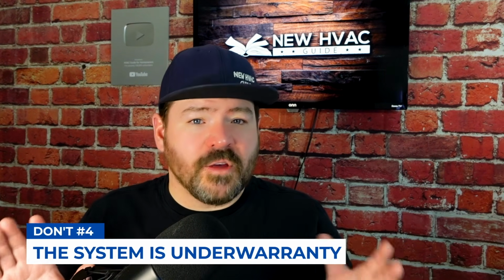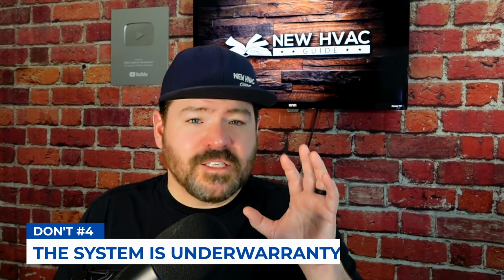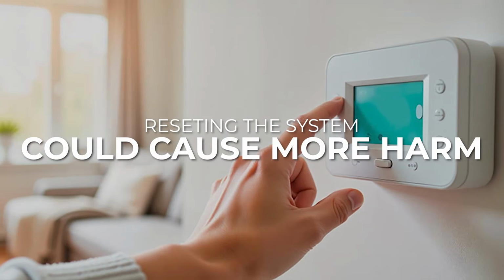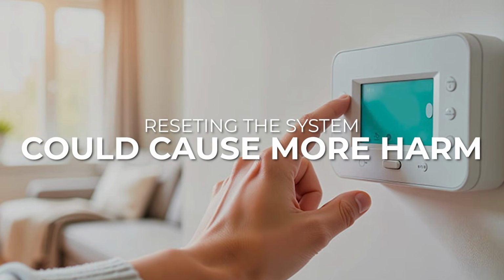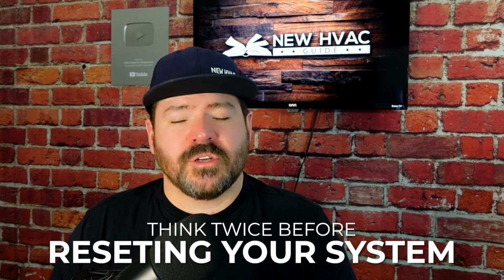Number 4, the system is under warranty. I don't want to do anything that voids my warranty. If that system has now tripped out, resetting that system could cause more harm than good, and now you have a problem on your hands where you've made the problem worse, and you may have even voided the warranty. So if I've got a newer system under warranty, I might think twice before I actually reset that system.